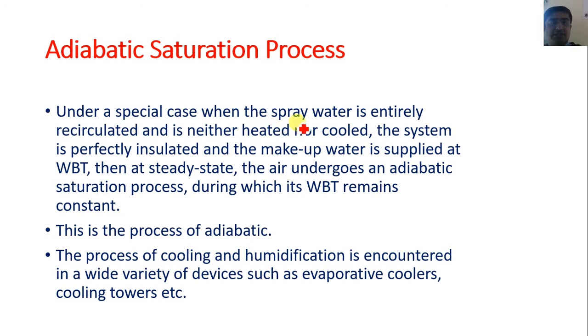And under a special case, when the spray of water is entirely recirculated and it is neither heated nor cooled, it means that it is entirely recirculated and there is no effect on the temperature of water. So in this case the temperature of water remains the same in the entire circuit. It is neither heated nor cooled, the system is perfectly insulated, and the makeup water is supplied at the wet bulb temperature.